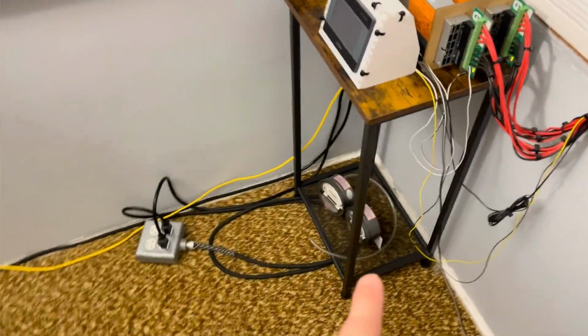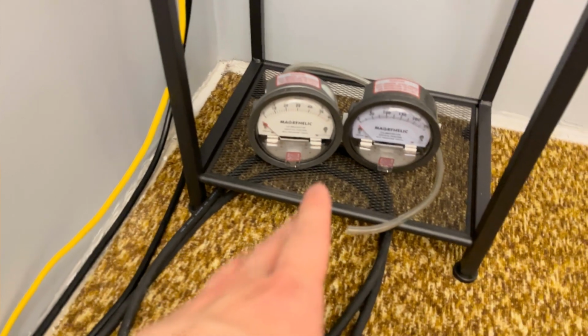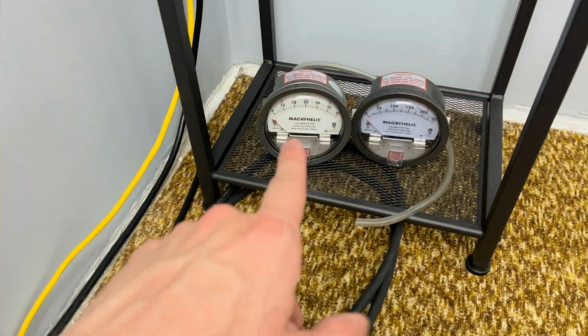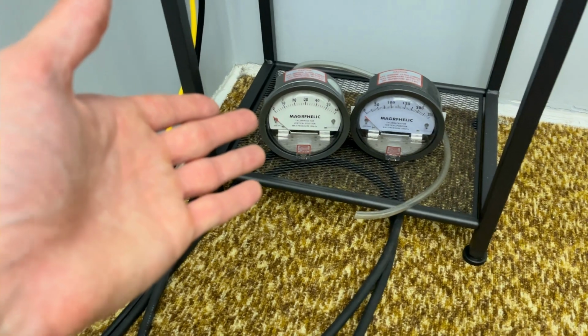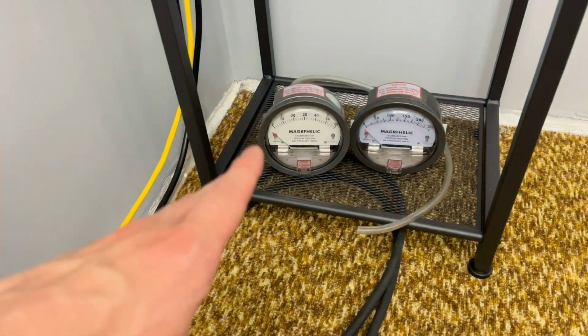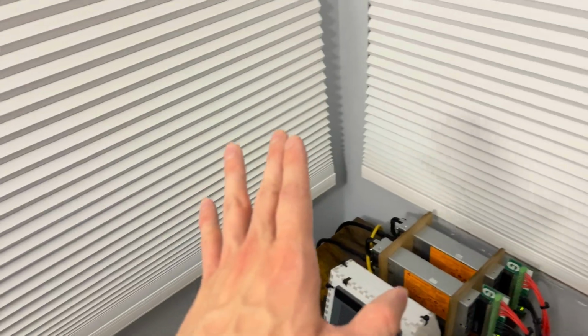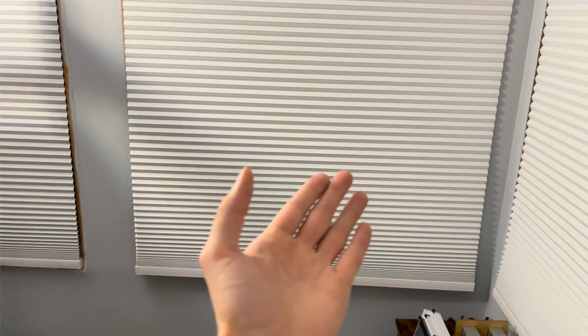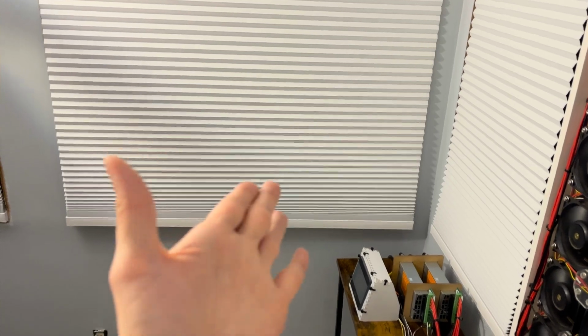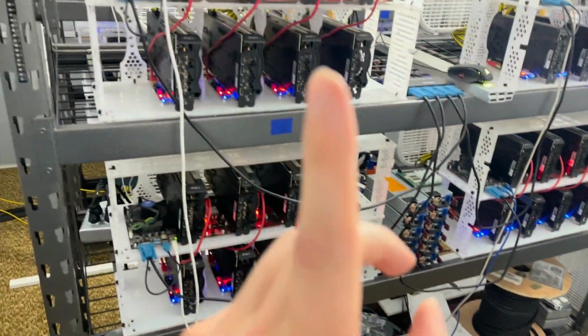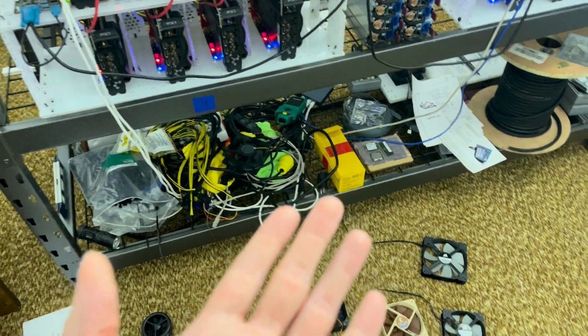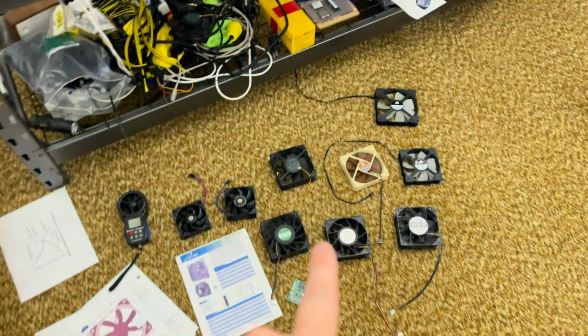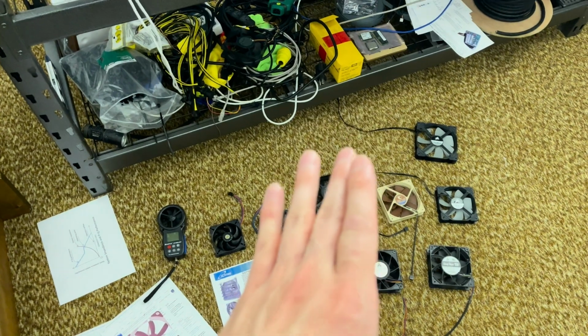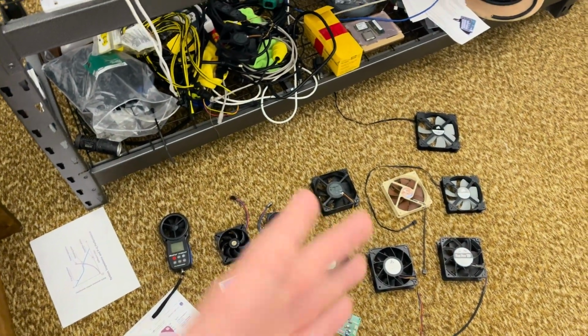And you could also get things like this, pressure meters. There's digital ones. The analog ones are kind of inexpensive and can be more accurate for low pressures. These work great, give you an indication of your current system pressures, but of course they only work in environments where you could seal one side from the other. So in this environment, you know, we got a small room here. There's the outside on the other side. There's a window there I could stick a tube out. It's easy to do, not always possible, but something to keep in mind, static pressure is a real killer. It's the typical thing that causes your fans to not work as well as you think. Something to keep in mind, really gotta watch out for.